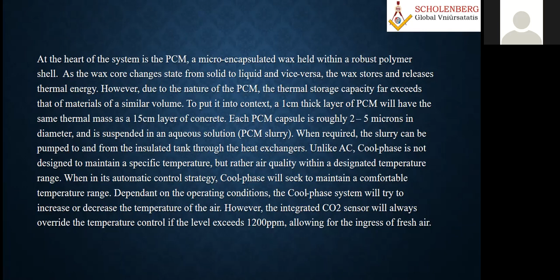So it's not designed to maintain a specific temperature, but it will maintain air quality. However, the integrated CO2 sensor will always override the temperature control if the level exceeds 1200 ppm. In basic terms, the cool phase system operates fully automatically under conditions of fresh air, cooling, and heat recovery. Under cooling conditions, the PCM absorbs heat from the air, and in heat recovery mode, the PCM is used to temper the incoming fresh air.